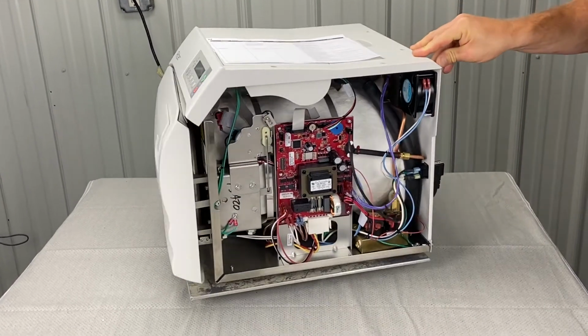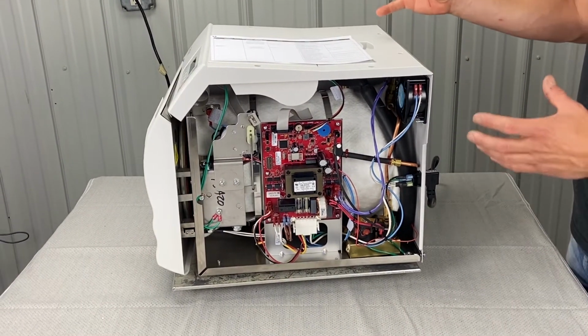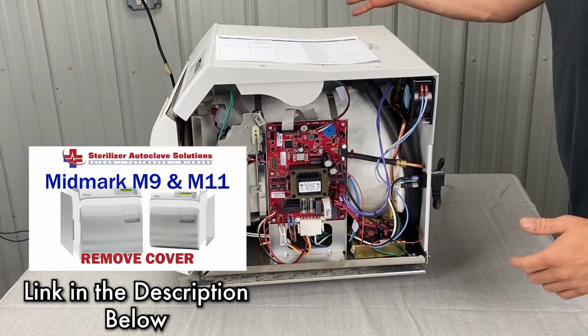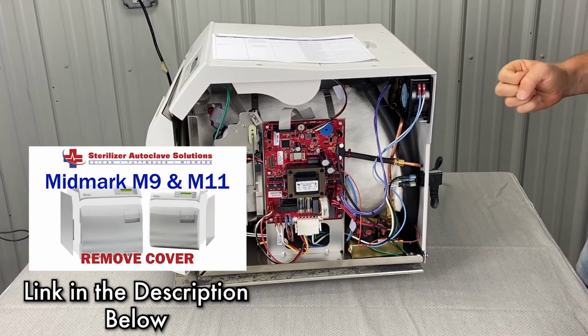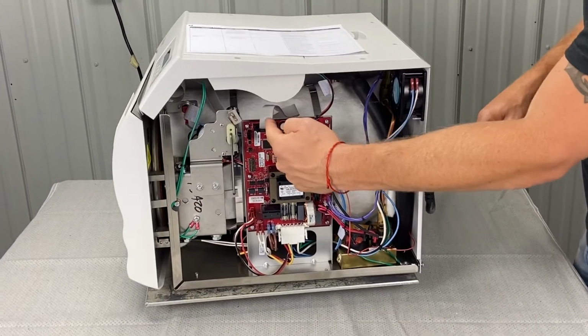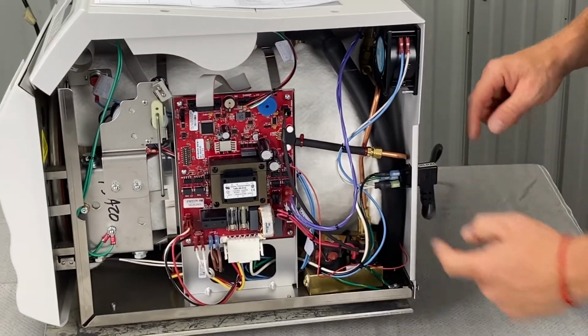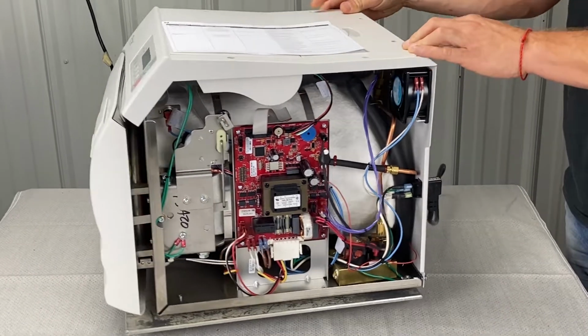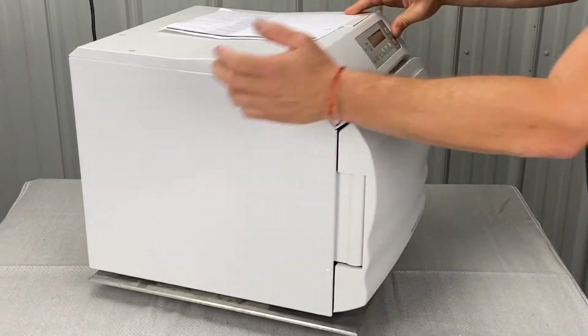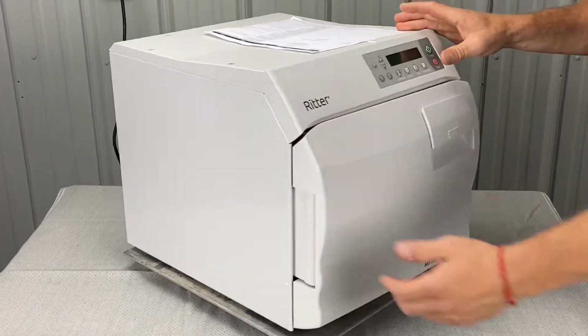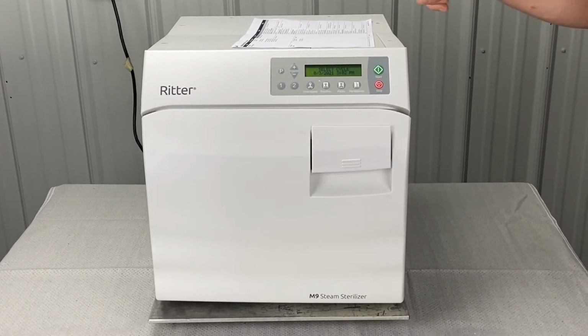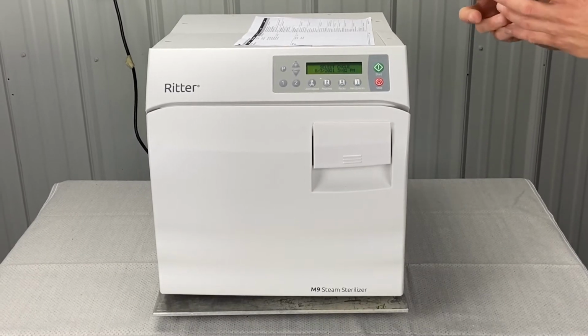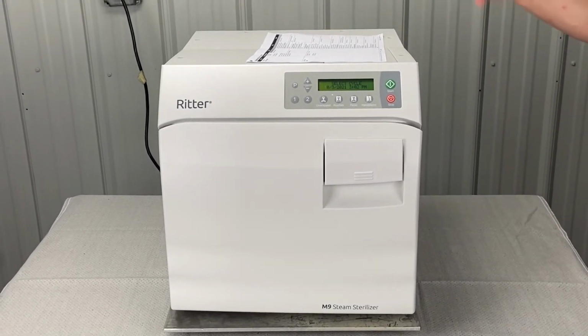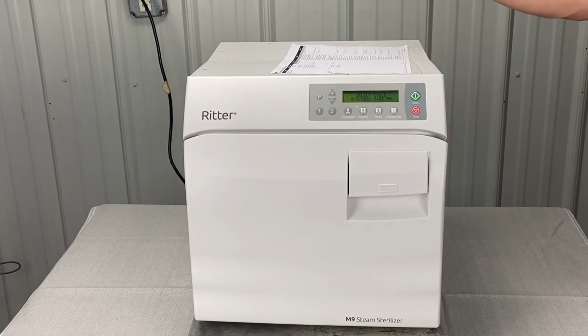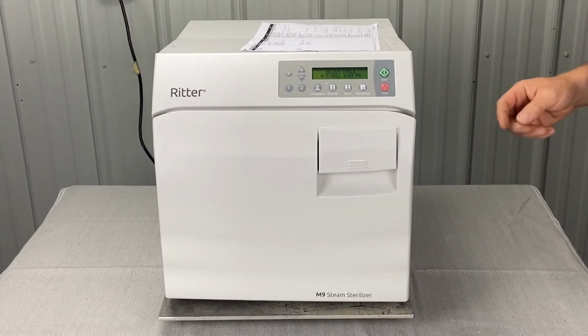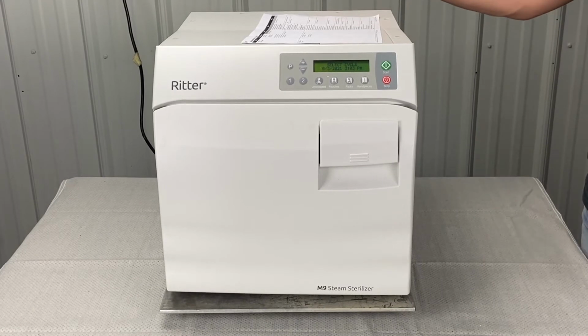So if you have patience to do that, we can walk you through it. You're gonna have to take the left side, right side panel off, top cover off, back panel off, and then we still have to leave the top cover plugged in here and the power cord plugged in so that you can run a cycle, but you'll have to get to the reservoir, which is over here. Inside of there's a condensation coil. You never want to see it dripping through there during the heat up part. As it's purging and condensing, it will spit out. But if you're running a test cycle and you're seeing water flow out and drip, then that usually indicates a leak in the air valve.